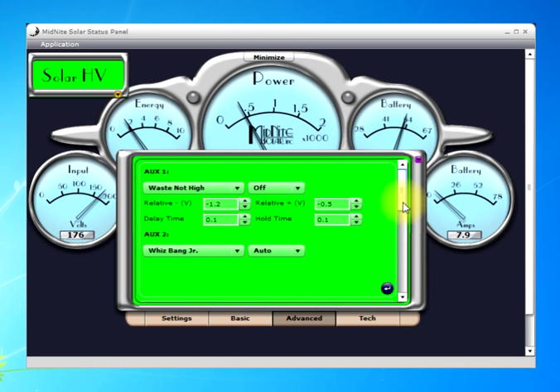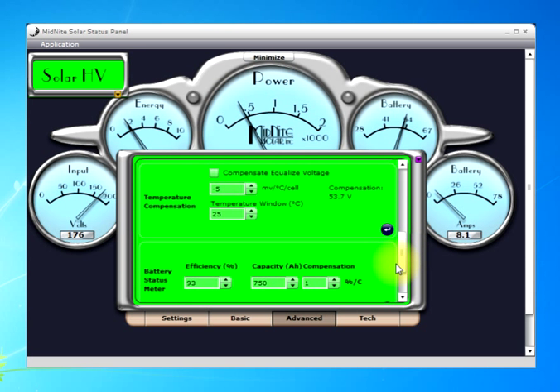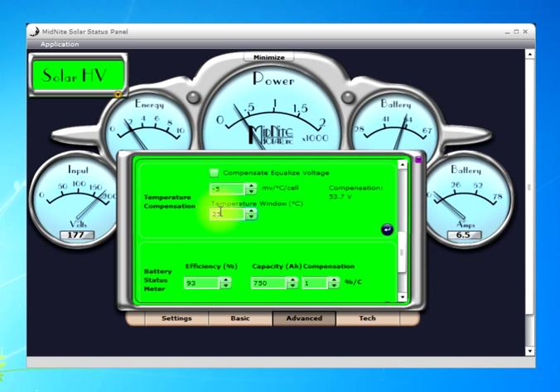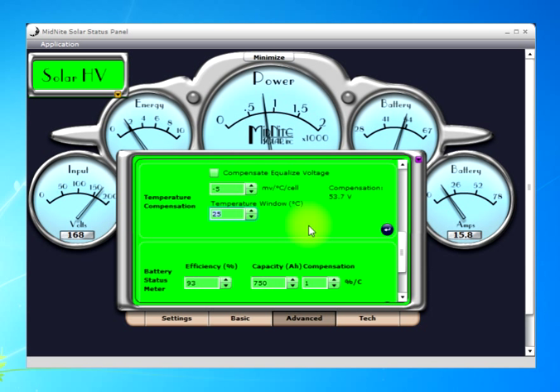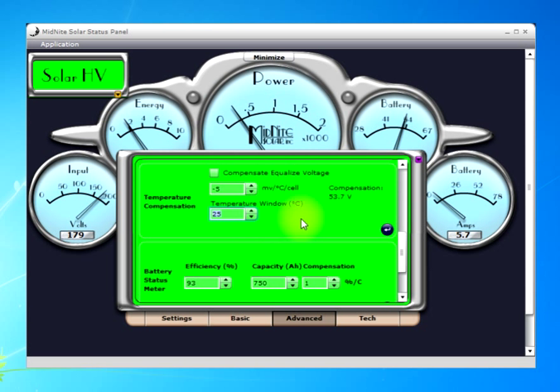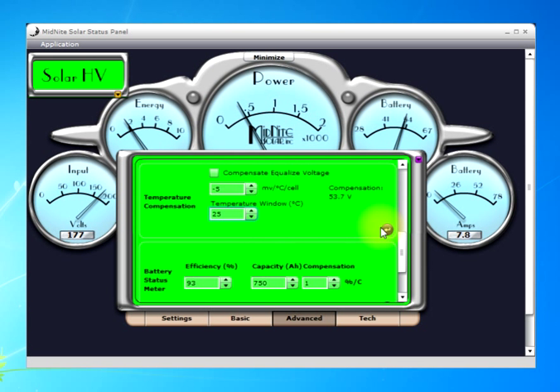That information was just written to the Classic, and now we need to finish programming the Whizbang Jr. Here's something that pertains to it — this 25 degrees C. This is the neutral point, or the reference point, for the battery temperature. When a battery goes below this number, the voltage you're charging to will raise and the capacity of the battery in amp hours will lower. When the temperature goes above this number, the voltage we charge to will lower and the capacity will raise — though higher temperatures damage the battery and shorten its life. This number is typically 25 degrees C by default, but a few manufacturers want a different number like 30 degrees C, so you'd use the up and down arrows and commit it.